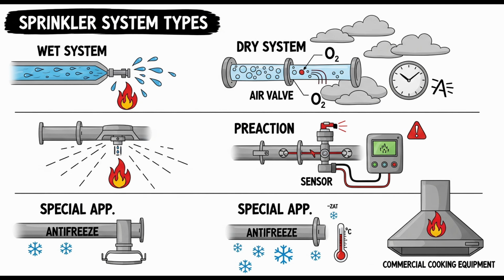And here's another one of those incredibly specific details. When check valves are used for subdivision in heated enclosures, they need a tiny hole. Yes, a 3/32-inch, which is 3 millimeters, hole must be drilled in the clapper of each check valve used for this subdivision purpose. A hole in a valve meant to stop flow. Again, that sounds completely backward. It does seem odd at first glance, but it's brilliant engineering. That small hole allows air pressure to equalize slowly between the different sections of the system divided by the check valve. Equalize air pressure. Why?